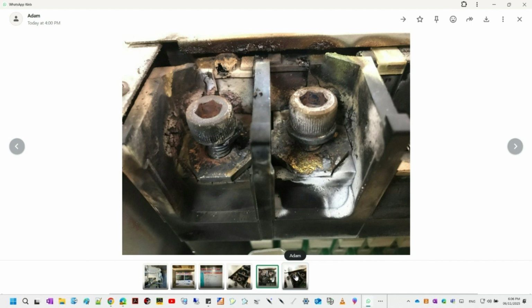And what's really telling about this approach is how systematic they were, the questions they started asking. They were seeking context beyond just the immediate fault. Exactly. They wanted to know, was there a maintenance plan in place specifically for checking electrical cabinet connections on these types of machines? And crucially, if there was a plan, did it specify the correct torque values for those critical bolts? Because that detail, as we'll see, turns out to be incredibly significant. And how often was the plan followed? What was the frequency?